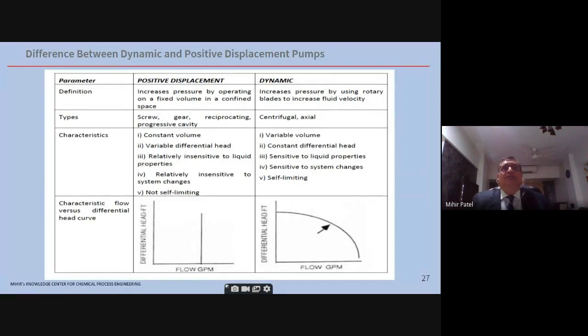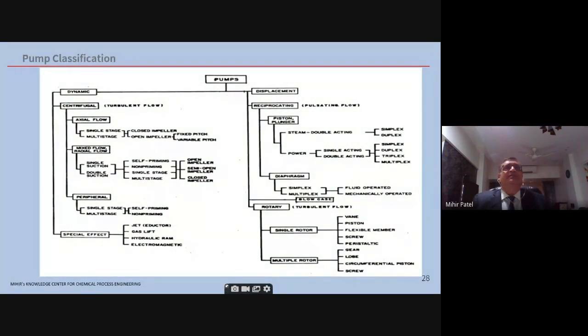So this is the performance curve, as you see at the bottom. This is the typical centrifugal pump performance curve. The arrow is the design point, okay? Certain design point, which is the best efficiency point, BEP, what is called. Now the pump classification is as shown.